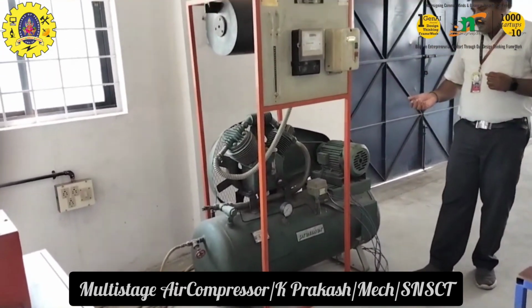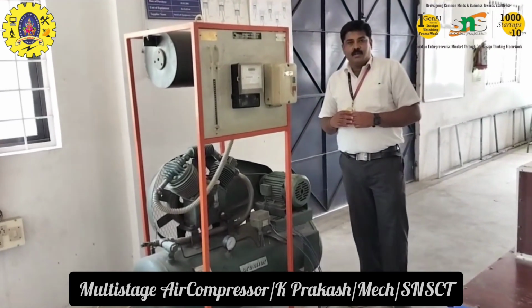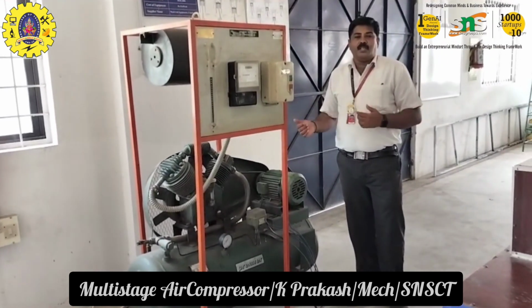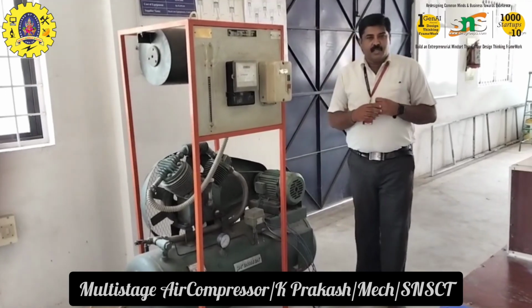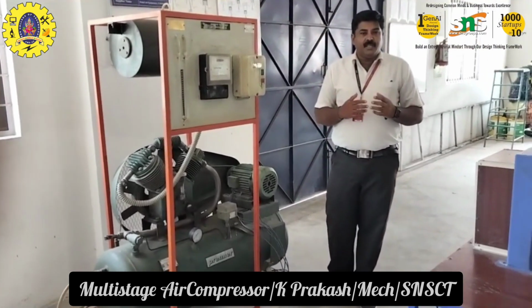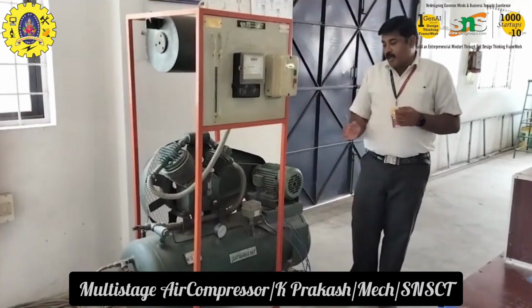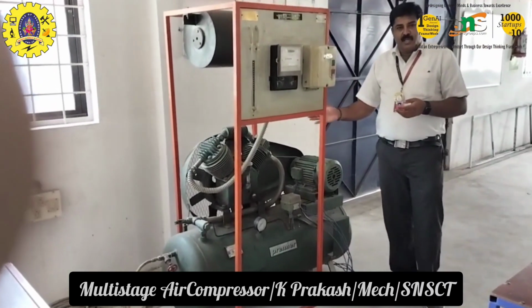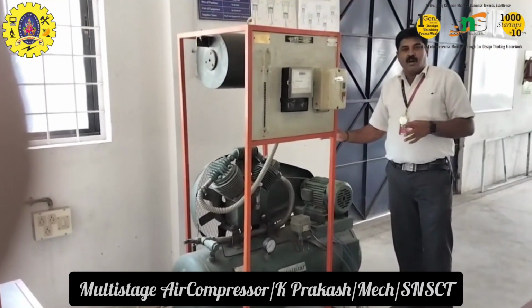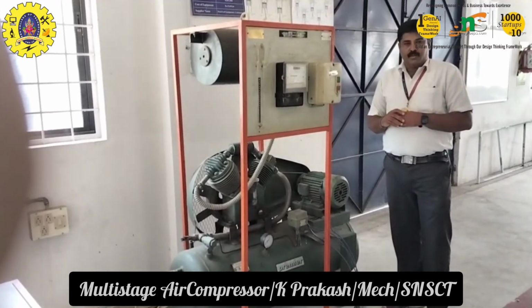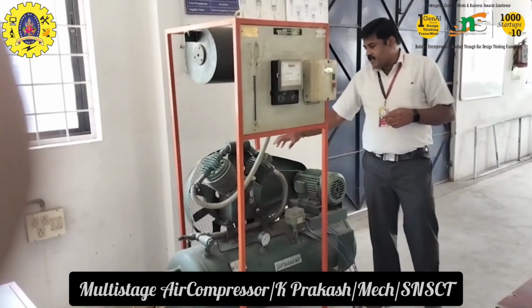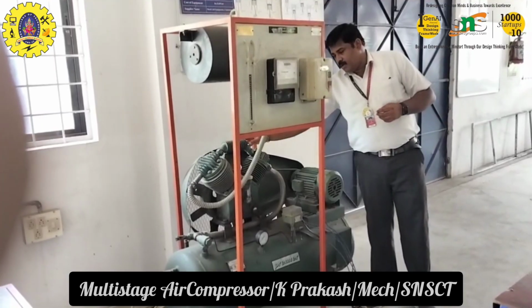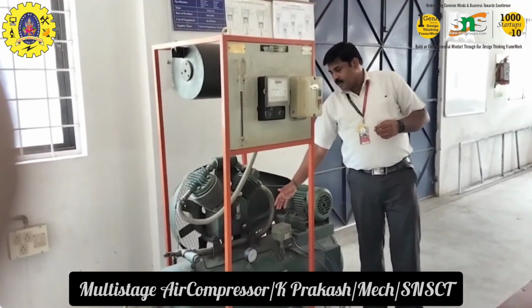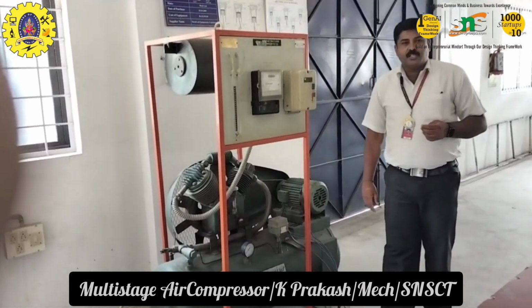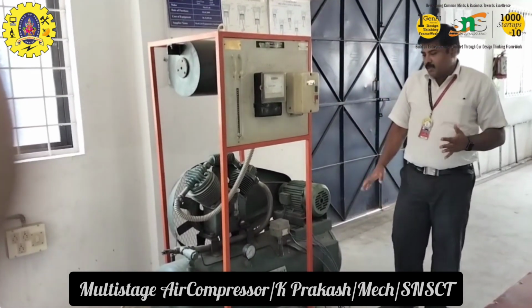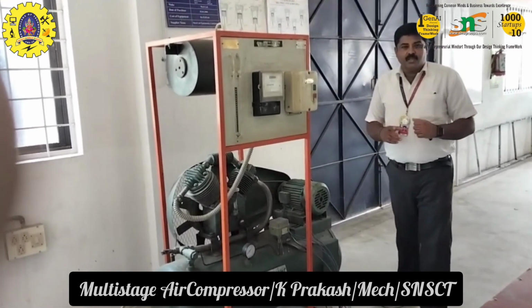What is the advantage of this? In multi-stage compression, the first advantage is that the required level of air pressure can be reached. The compression may be single stage, two stage, three stage or four stage according to the required level. In this multi-stage compression we have an intercooler in between and then the receiver tank, and the work done is reduced when compared to single stage compression.